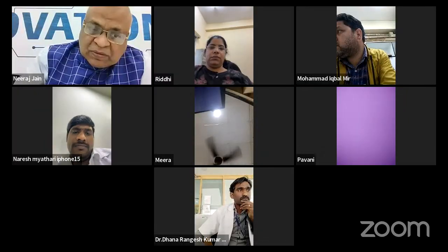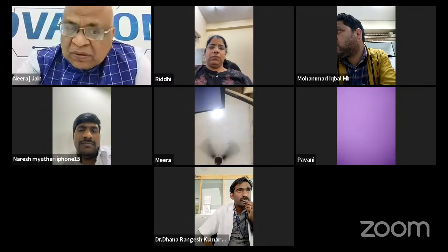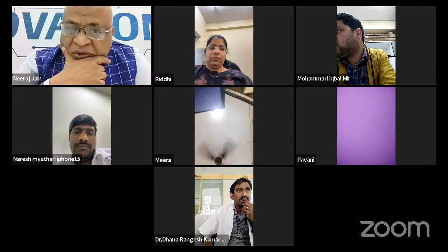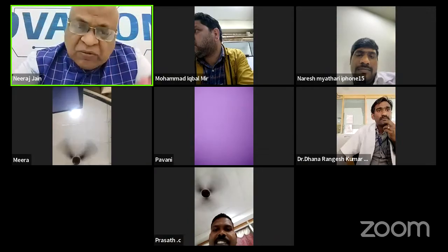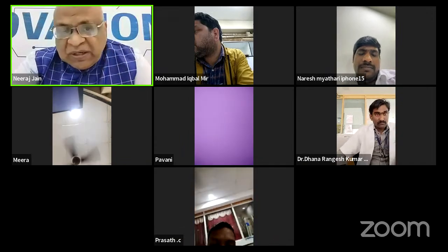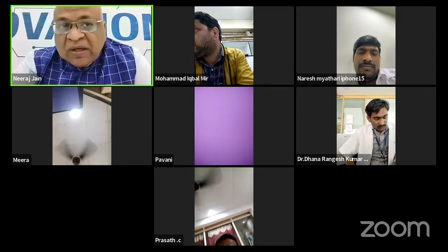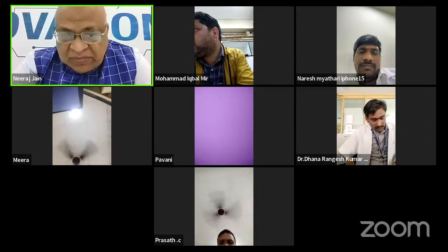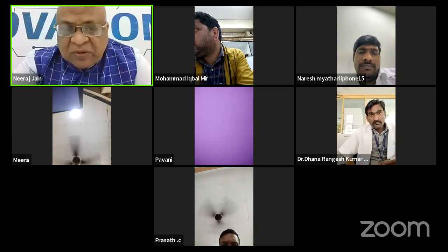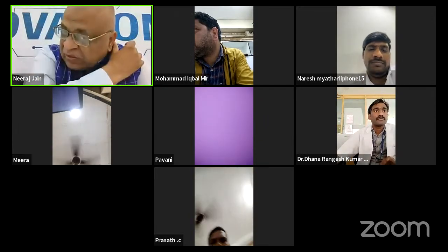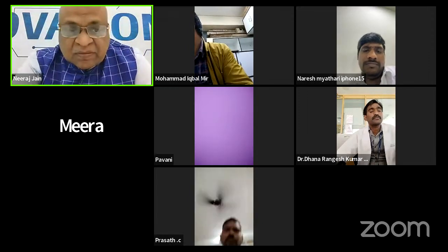Thank you, sir. Another question. Is linearity, as you mentioned, mandatory or optional? It is mandatory. Once in 12 months, you have to perform this linearity. It is not optional, because for linearity, carryover, precision, you are checking with controls, but these things also shall be checked in quantitative analyzers.